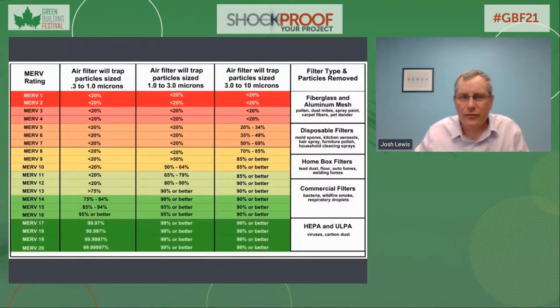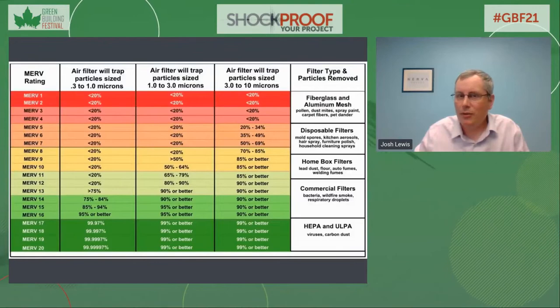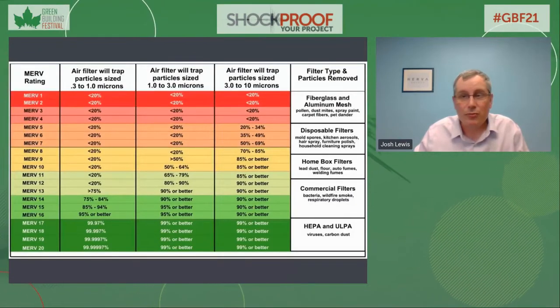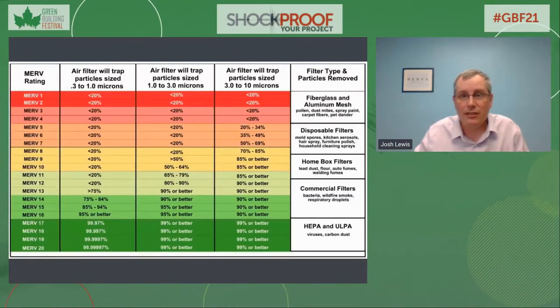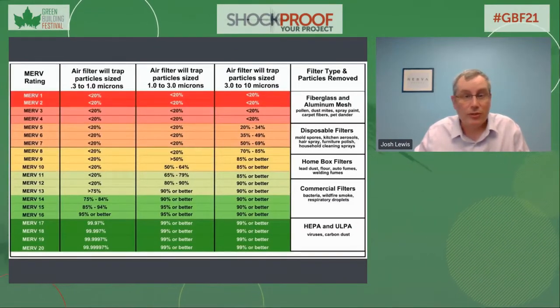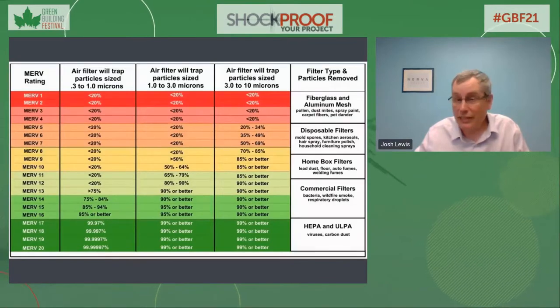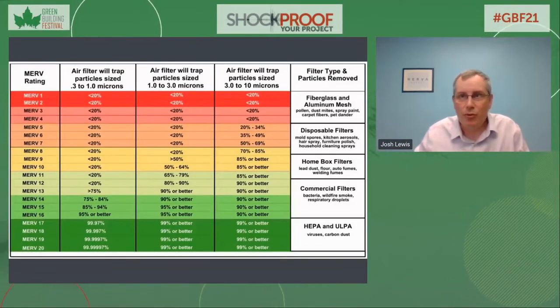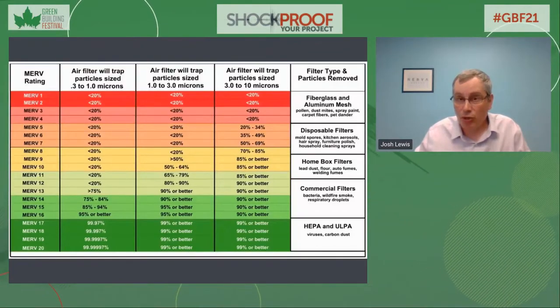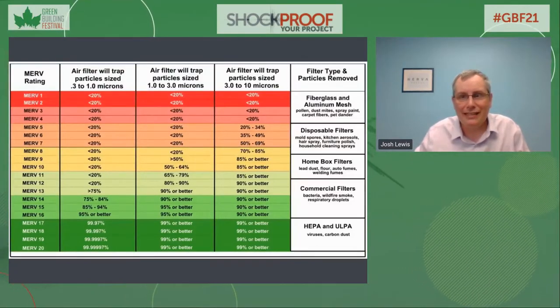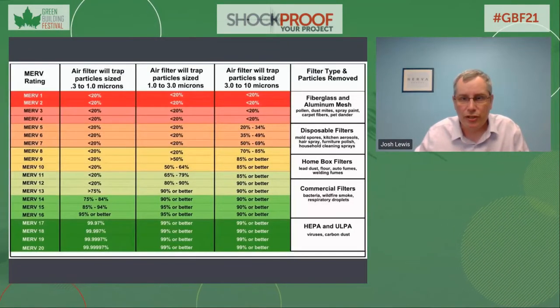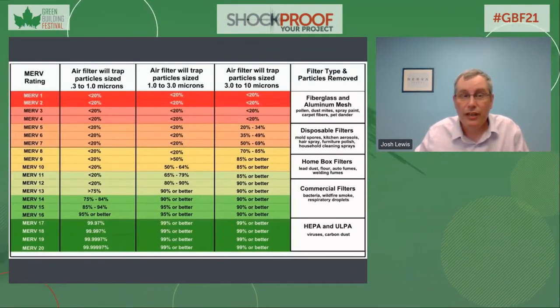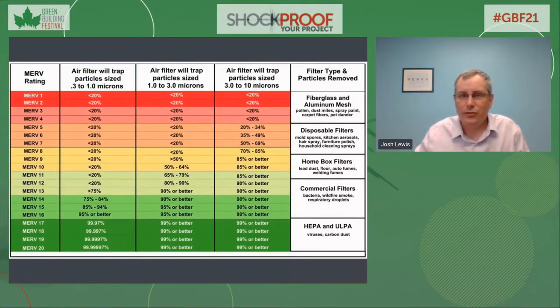Filtration is the first key operational parameter that must be optimized. Filters are present in virtually all HVAC systems, and they're designed to trap various contaminants in their collectors. Their performance is critical, as they must be capable of cleaning the air as it's passing by.